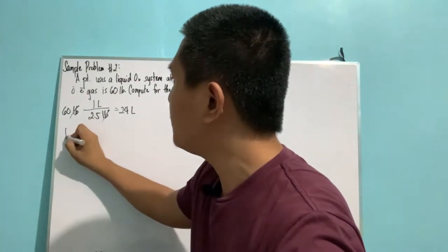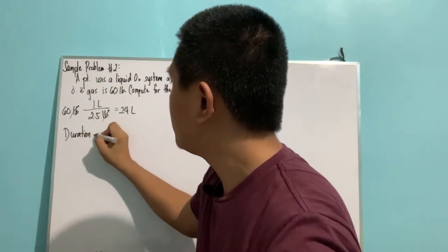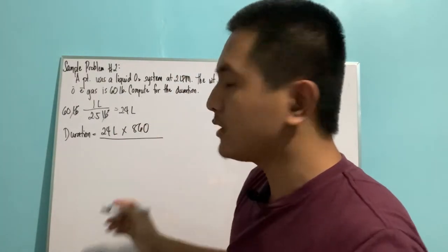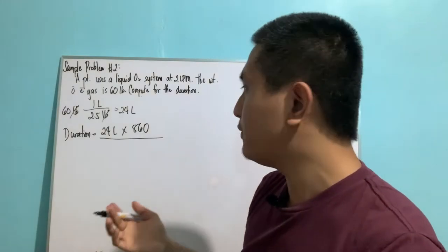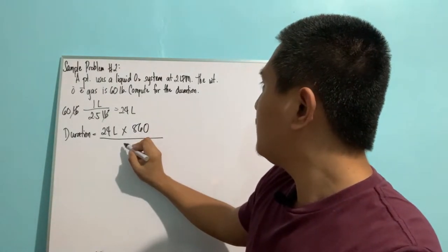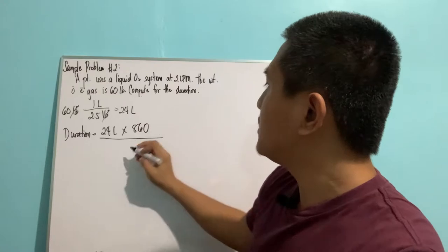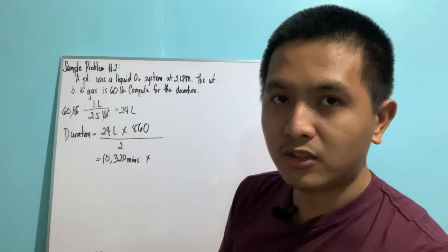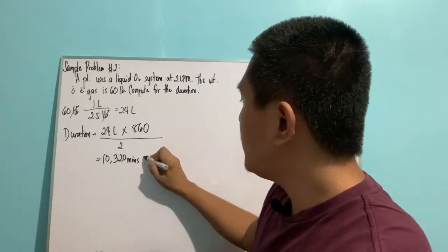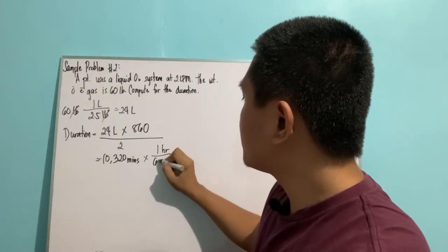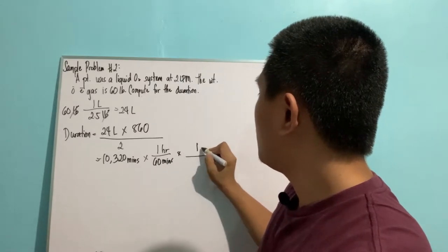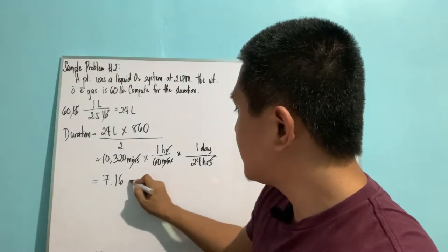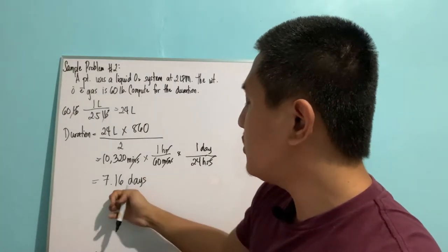60 divided by 2.5 gives us 24 liters of liquid oxygen. We can now proceed with the formula: duration equals 24 liters of liquid oxygen multiplied by 860 liters of gaseous oxygen — the conversion factor — divided by the flow rate of 2 LPM, giving us 10,320 minutes. We need to convert this into days. 60 minutes per hour and 24 hours per day gives 7.16 days.